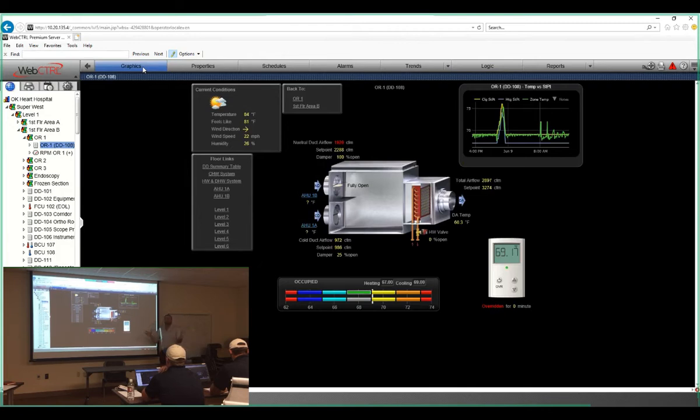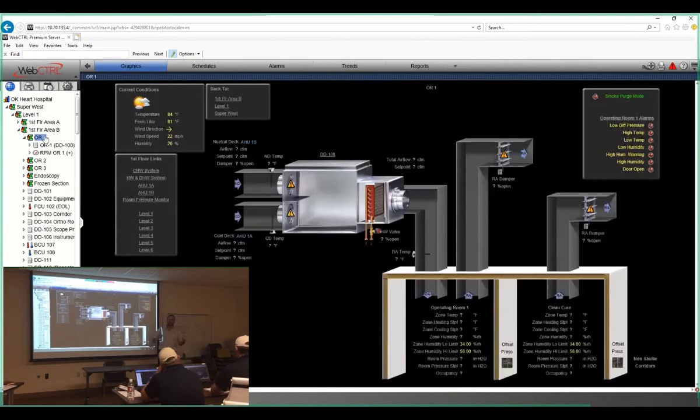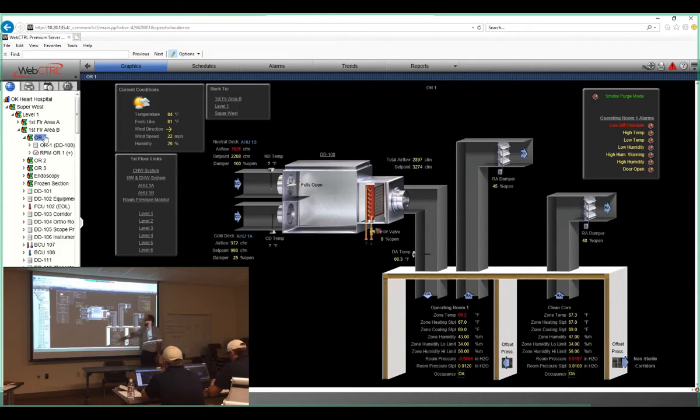It's really pretty simple. We started to put all the flows in the VAVs, and it was a little more complicated than just making it simple, using cubic feet and making adjustments, and that's what this does. It tries to track it. So to maintain the air changes, we're at 3275. The VAV is going to try to maintain that between the cold deck and the neutral deck.